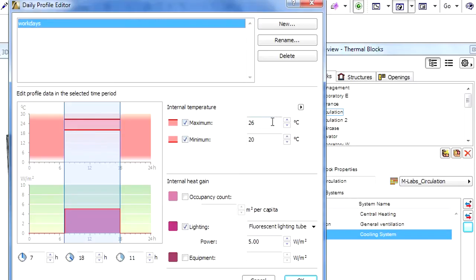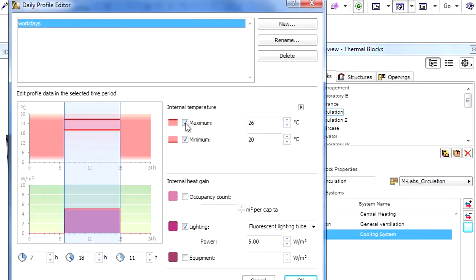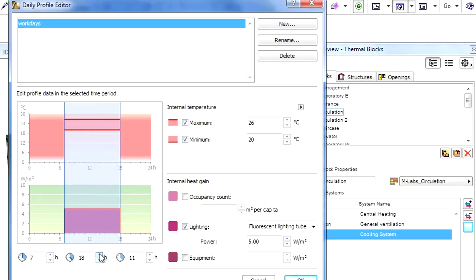If the temperature rises above the maximum or falls below the minimum values provided at the Operation Profile, then the energy demand of a cooling or heating system will be automatically added to adjust the overall energy demand. If no minimum or maximum internal temperature value is set for an Operation Profile, then the internal temperature will be influenced only by the building envelope characteristics and by the external weather conditions. In this case, no energy demand adjustments will be carried out in the corresponding thermal blocks.